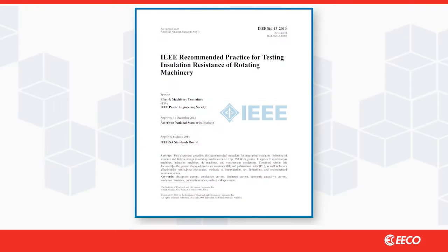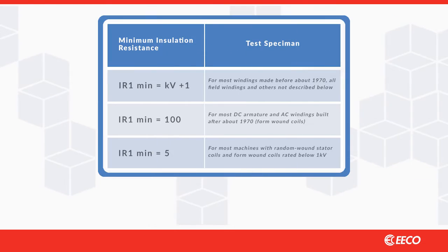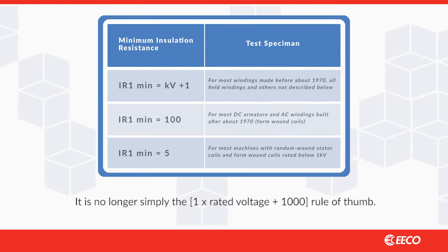IEEE 43 provides the guidelines for the test, which underwent considerable change in 2000 and was further revised in 2013. For example, most form coil windings manufactured after 1970 should have a minimum of 100 megaohms for operation. Again, that is the minimum.